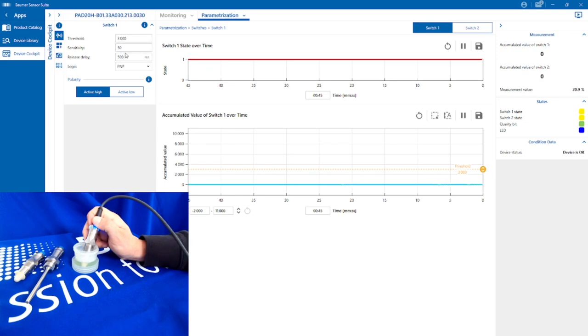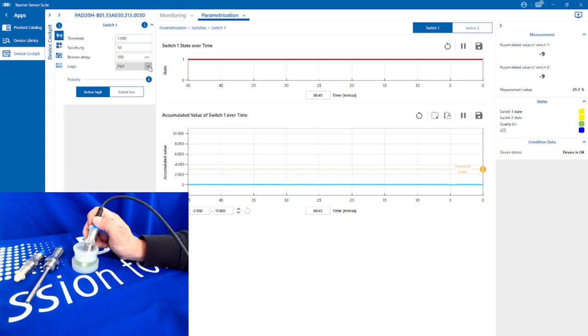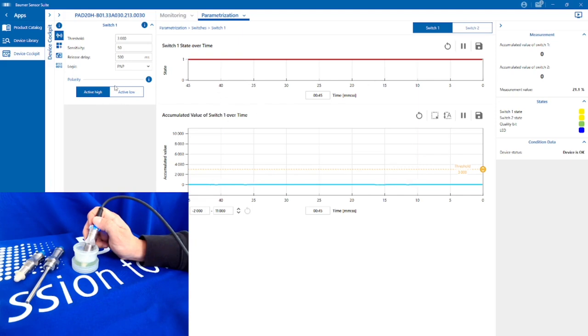I've also set a half a second response delay and release delay, so I need to see the accumulated value steady for around half a second before I get an affected output, and that can be adjusted accordingly. For logic, I've got PNP output, but we can also use NPN, push-pull, or we can actually disable the output. So if we don't want two outputs we only want one, we can disable one of them. And the polarity I've got active high; I could turn that to active low if necessary.